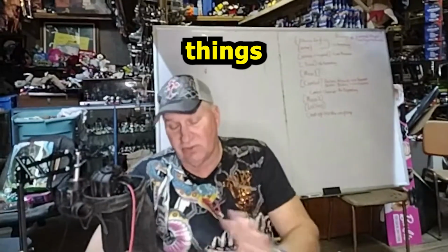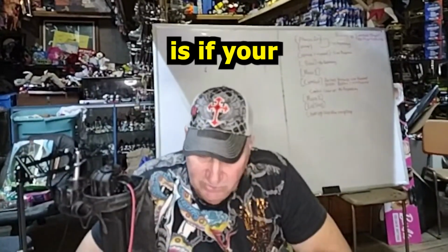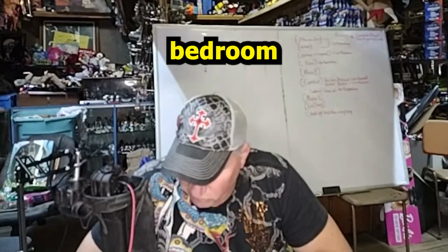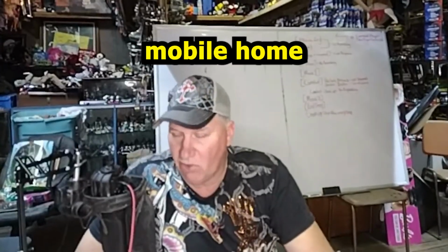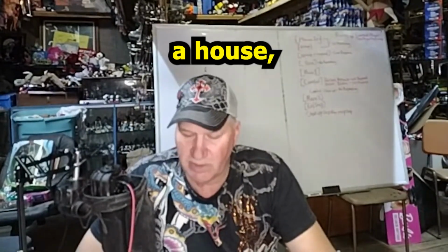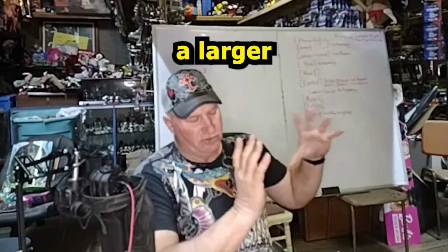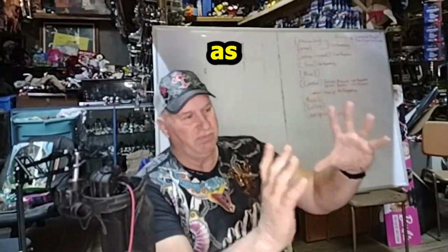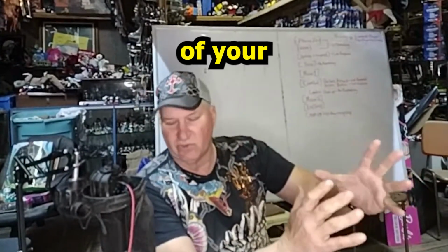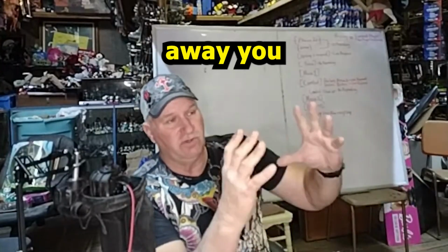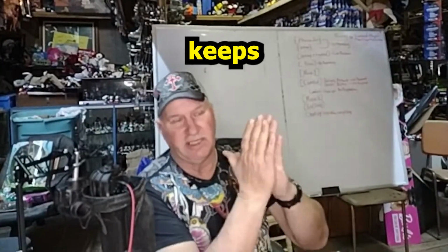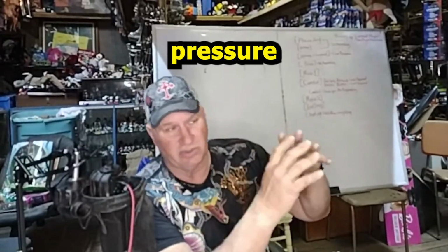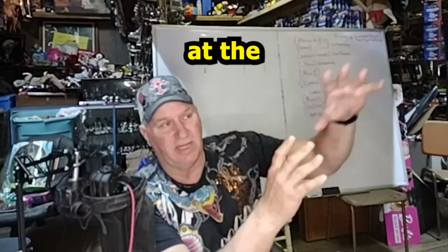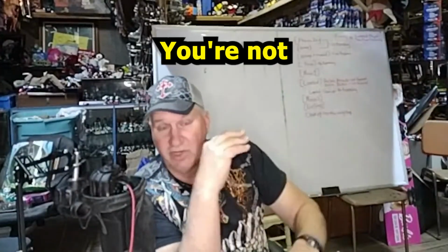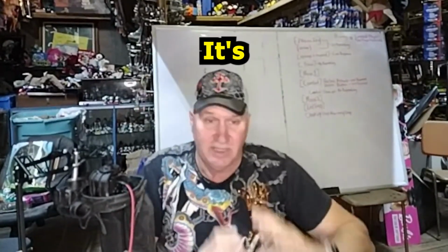I'm not saying any of those is necessarily your problem. But if your master bedroom is all the way at the end of the house, that's a unique issue for single or double wide mobile homes. In a regular house, you'd use larger ductwork, say 14 inch, near the main source of heat, and reduce the duct size the further you get from it, sort of like hydraulics, to keep the air pressure consistent. With a mobile home, the ductwork stays the same size the whole way.